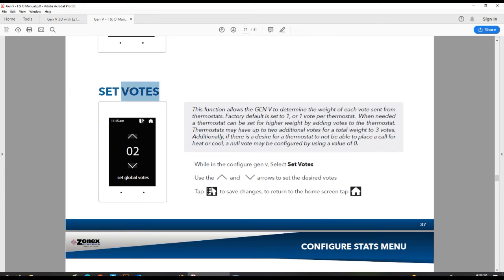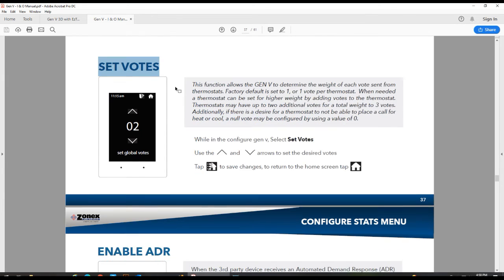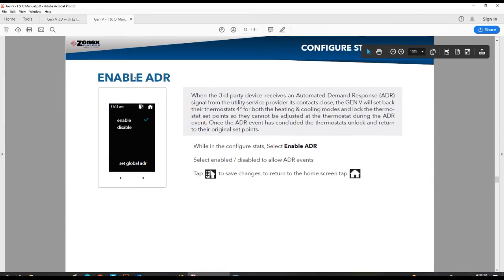And then setting your votes. This is a majority vote based system, so they all come set up from the factory with 1 vote. If you'd like to give them more votes, you can. We go from 0 up to 3 votes. 0 gives you no value, or what we call a null vote. It will not be seen by the system. And then up to 3 votes if you want. Enable ADR. If you're using the ADR, automatic demand response feature, you want to make sure you enable this so the system recognizes that demand response.